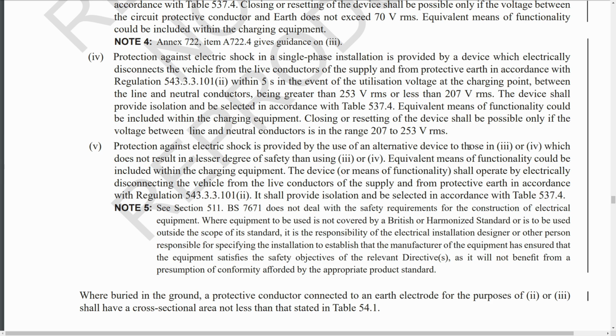But it is possible for at least some of those properties to have the voltage between line and neutral within this range, but crucially the voltage between the true earth outside and those two conductors could be more than 70 volts, which would still result in a dangerous electric shock if someone was, say, standing outside and touching the car or some other exposed metal part. So this is certainly an option to use, and it will be useful in some instances, but crucially not all instances.